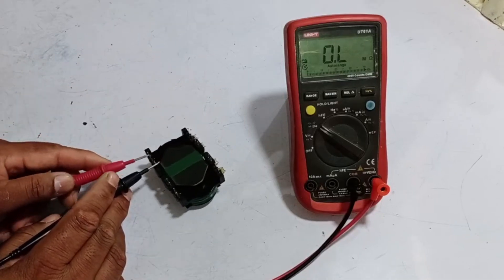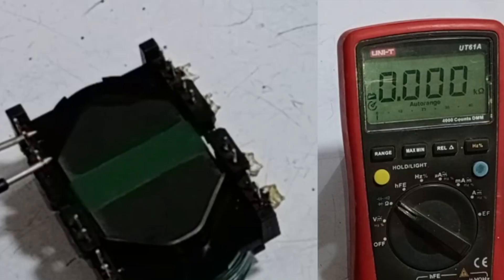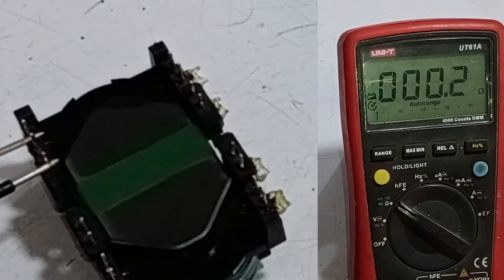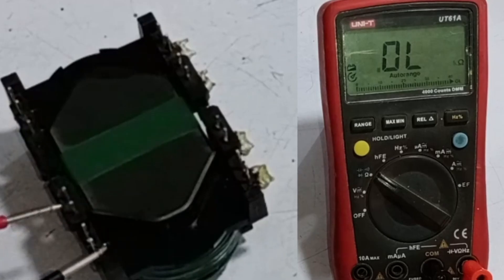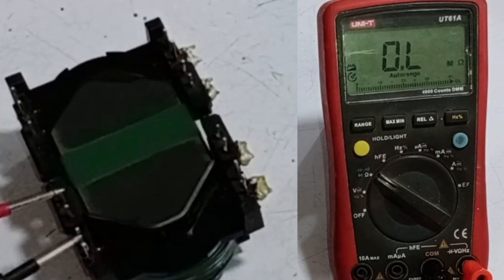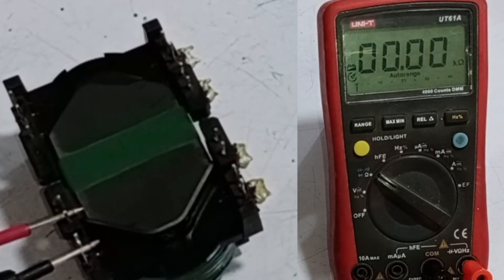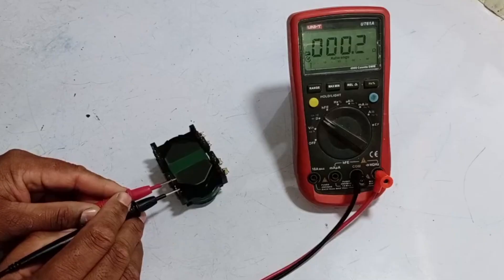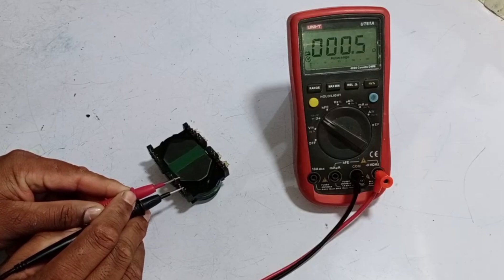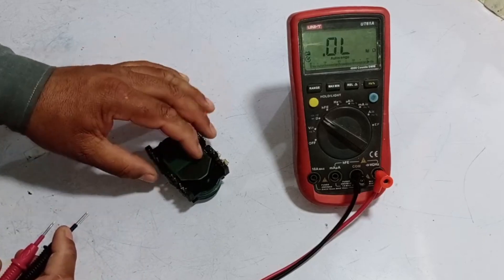Now, the testing of these other wires will be done as follows. You should observe a small resistance here, but the value should not be too high. If the resistance increases significantly, it indicates that the reactor is faulty. Additionally, if any of these wires disconnects, the reactor will not work properly, and it will need to be repaired. This is how you can test it.